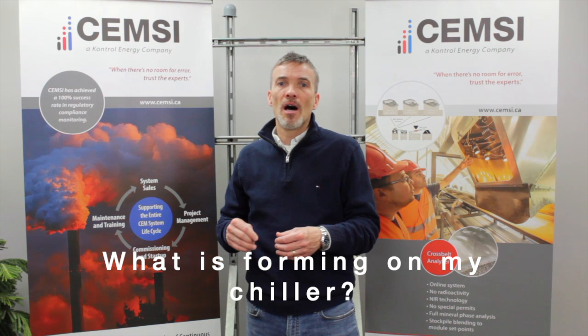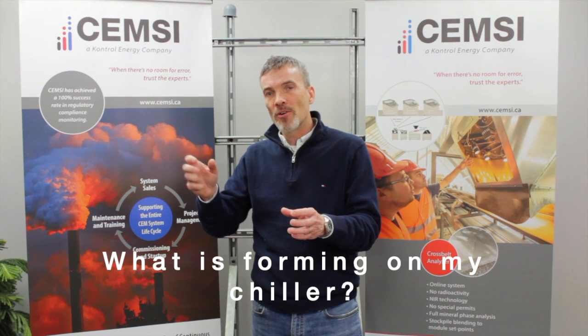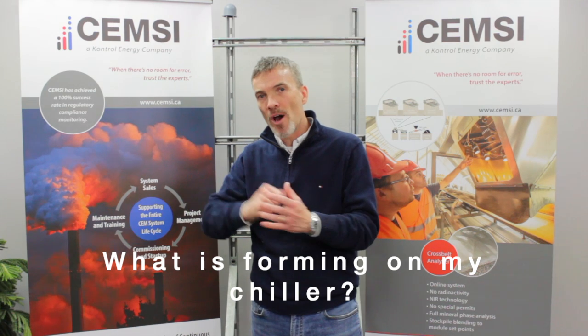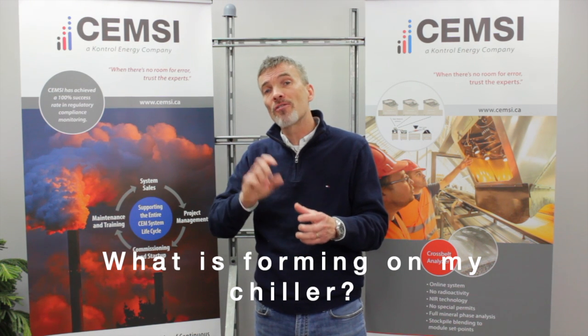The key to it is, we've had some customers say, oh, I think this is actually particulate. They think it's a hydrocarbon-based product. But it's quite simple. Take your chiller, take that chemical salt that's formed, take a little bit of water in a lab squeeze bottle, and squirt the water in there. If it instantly dissolves, it's a chloride base.